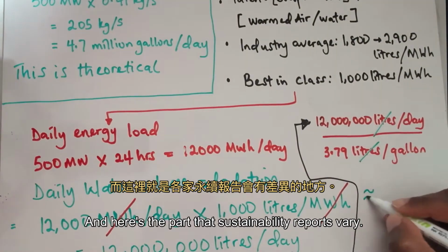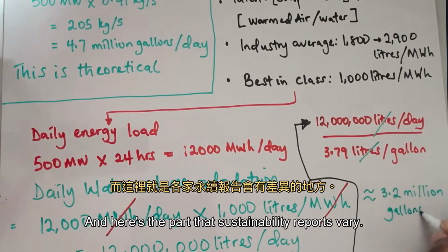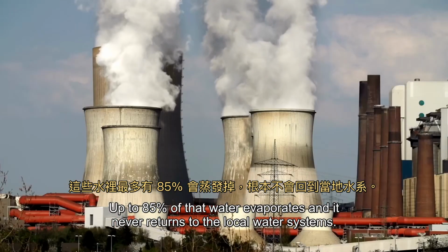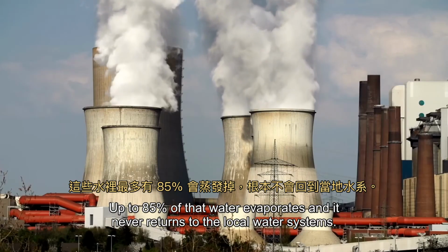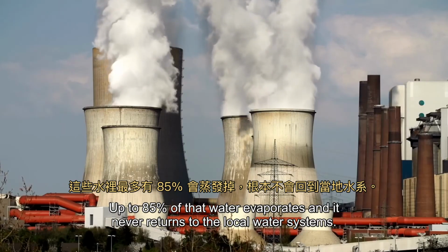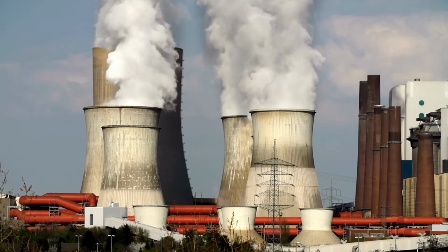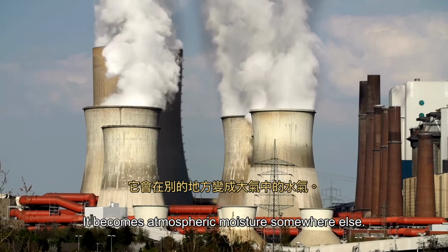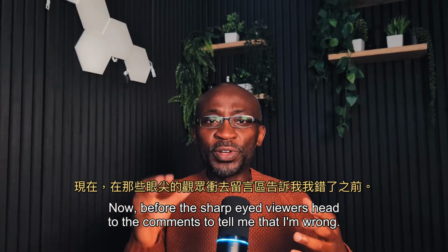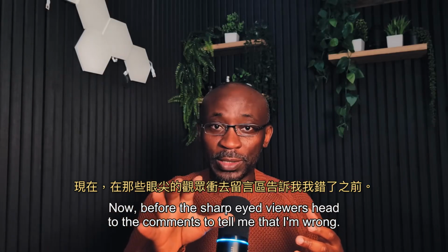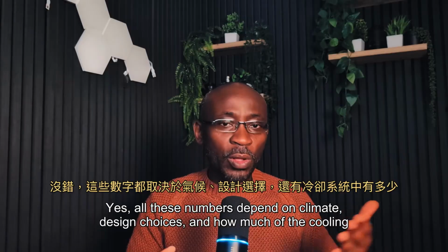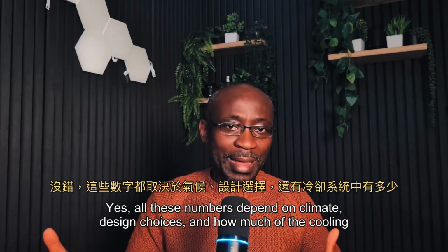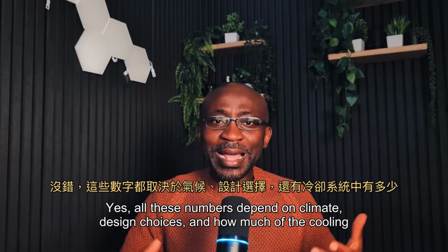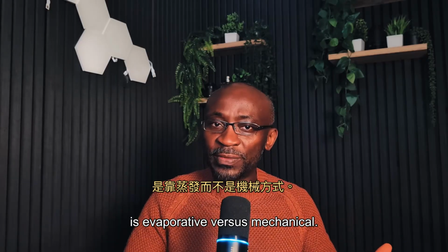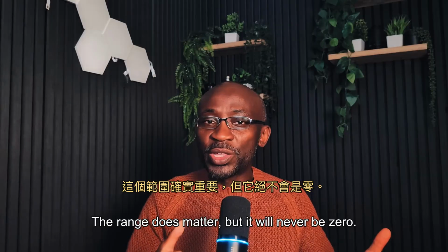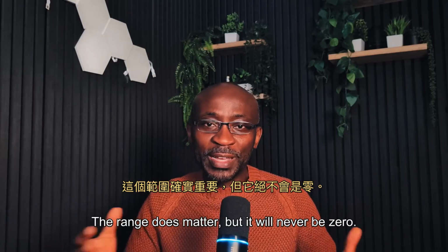And here's the part that sustainability reports vary. Up to 85% of that water evaporates and it never returns to the local water systems. It's just gone. It becomes atmospheric moisture somewhere else. Now, before the sharp-eyed viewers head to the comments to tell me that I'm wrong, yes, all these numbers depend on climate, design choices, and how much of the cooling is evaporative versus mechanical. The range does matter, but it will never be zero.